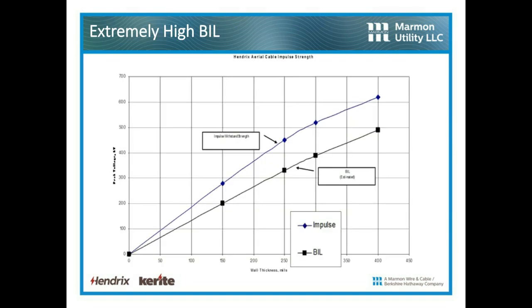Here's the BIL. If you look here at 150 mils, that's going to be a 15 kV system. So that cable, we'll give that cable about a 200 kV BIL. The system BIL, once I put the spacer in there, is going to be in excess of 300, 350 kV. And if we use a larger spacer, you can have 300, 400, 500, 600 kV BIL. So it's really a shockingly high BIL system. And here's the same for the 15, 25, 35, and 46 kV systems.